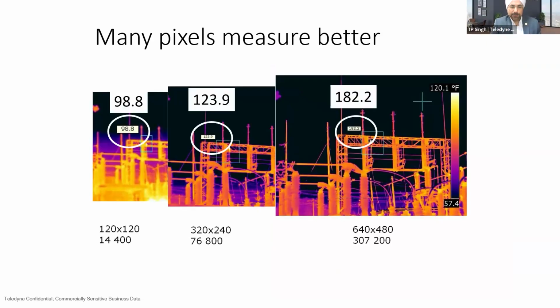For example, if you see the lower pixel image here, the temperature shown is 98.8. But the moment you use the higher pixel camera, the temperature is 182.2. Imagine if you are using the lower quality camera and then taking a decision based upon that - it is completely wrong, because this connector can fail even tomorrow. So it is very important to use the right product for the right application.